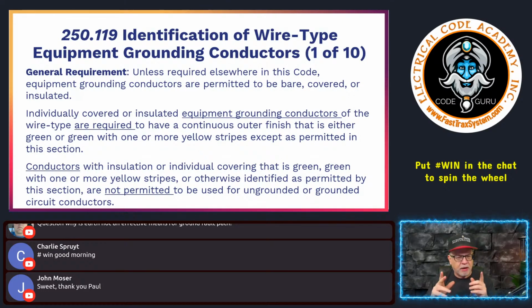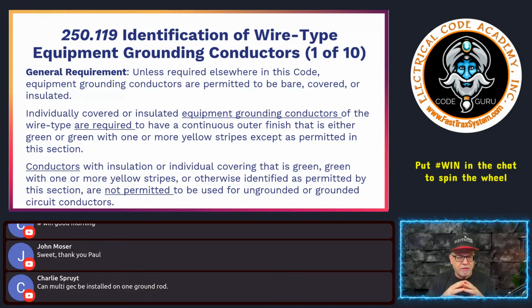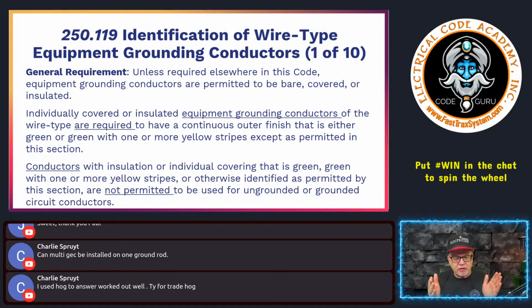It's a safety conductor. Now, an equipment grounding conductor is not part of a circuit conductor, right? Where you have the blacks and the whites and the reds. It's not a circuit conductor. So when you see the code talk about circuit conductors, it's not talking about the equipment ground. Although the code requires, 300.3, I believe, all of the conductors to run together. By keeping everything in close proximity, it removes the additional increased impedance that can come from reactance, capacitance, and all that kind of stuff. So at the end of the day, it's all how we route them, and that's why we put an equipment grounding conductor with the circuit conductors. Okay, that type of thing.